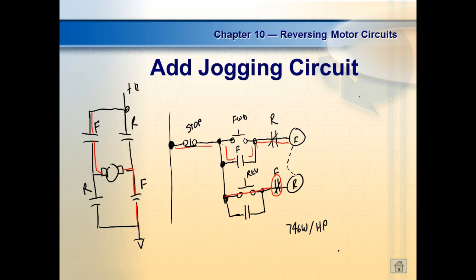So if I have a 5 horsepower motor and we work this out, it would pull a different current for high voltage. It'd pull less current for high voltage than it does for low voltage. That's why they put those things in. I can't put an internal overload, because an internal overload is going to look for one current, right? Because it's internal. An external overload, I can set it for the current that I want.